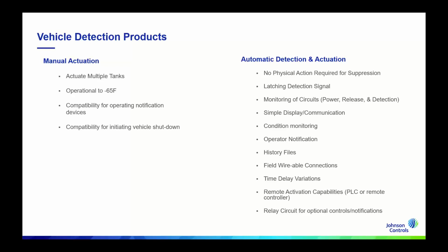The automatic detection and actuation system is designed and selected based on the ability for the system to operate without physical intervention, but having the ability for the user or operator to be able to fire the system is also valuable. Having the detection signal latch and register in the controller is also an important feature to look out for, as is the monitoring of the different circuits that exist. This gives us the monitoring capabilities so that the operator knows if there's an error or fault within the system, and the messaging is best provided with an easy to understand visual indication on a user display.